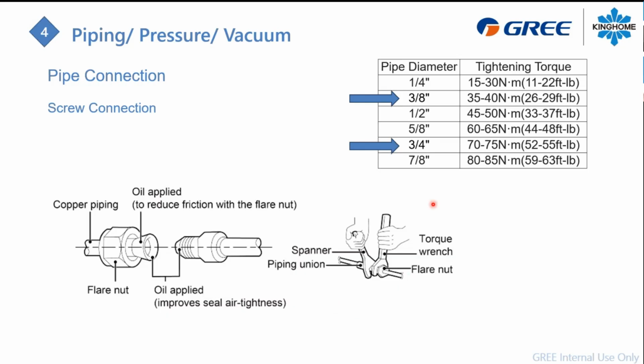So using your torque wrench, be sure you apply the right torque on it, because it's a 3/4 flare connection. It's hard to know exactly by hand how much pressure you applied on that connection. So using a torque wrench is a must. It's really important to know exactly how much pressure you push on this little nut right here.